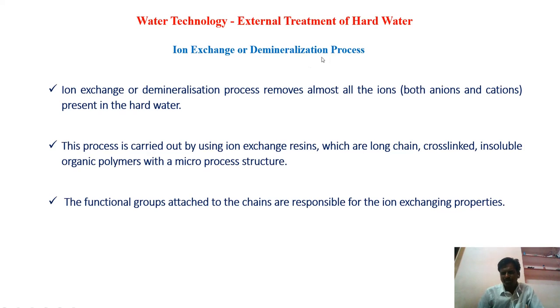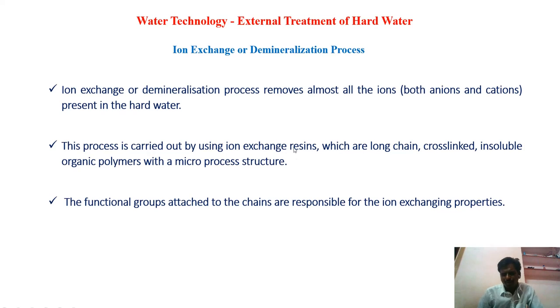Demineralization means removal of calcium and magnesium ions from the water. In this process, almost all the ions — both anions and cations — can be removed. That is the main important feature of this process. In this process, we are using ion exchange resins, which are made up of polymer having a long chain cross-linked functional groups. These polymers are insoluble in water and are more hydrophobic in nature. We use these resins to exchange ions from water.